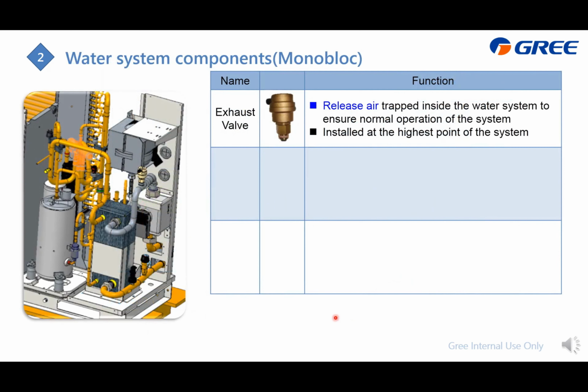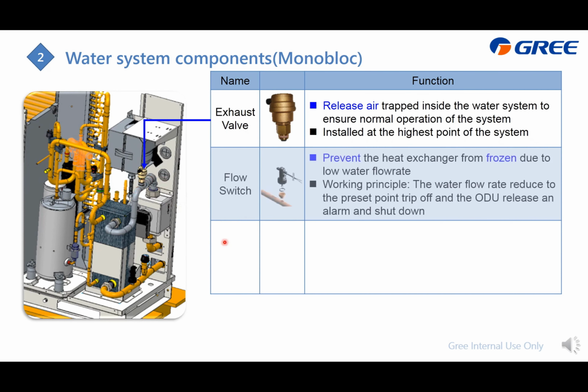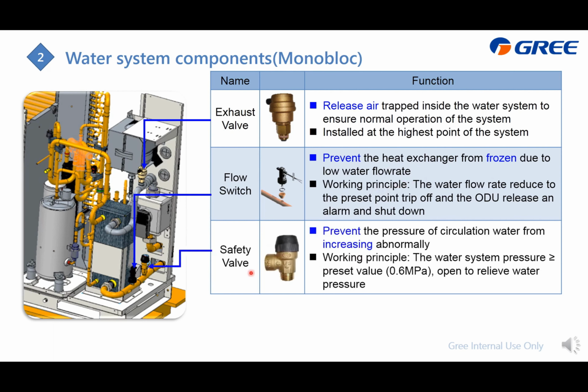This slide displays the water system components for the monoblock. Just open the panels, you will find the inside, and this is the plate heat exchanger. It exchanges the heat from the refrigerant system to the water system. And for the water system, we have the exhaust vent. It is also called the air vent, which is located here. And this one is to release the air trapped inside the water system to ensure normal operation, and also it should be installed at the highest point of the system, which is this highest point. And the flow switch located here is to prevent insufficient water flow rate, which may lead to freezing. And the safety valve is to ensure the water pressure inside is not too high, to ensure regular operation.